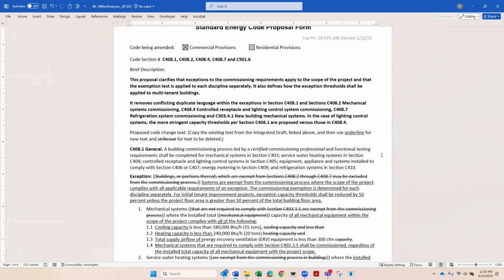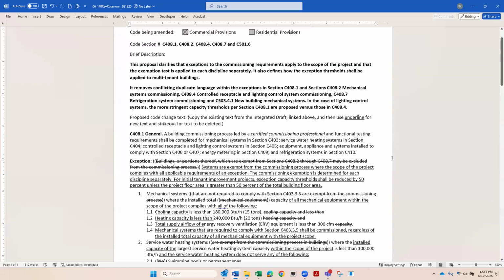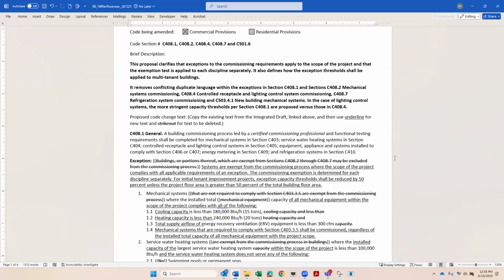In reality, when you've got a project that is a separate tenant improvement or a separate area, applying this at the whole building level is almost impossible for folks to sort out, especially if you have a tenant space being renovated. If whoever's responsible for that space has to go back and figure out the total capacity of everything else in the building to determine if commissioning applies, it's just too big of an obstacle. From what I've been hearing from commissioning professionals, this is a more appropriate way to apply those thresholds.